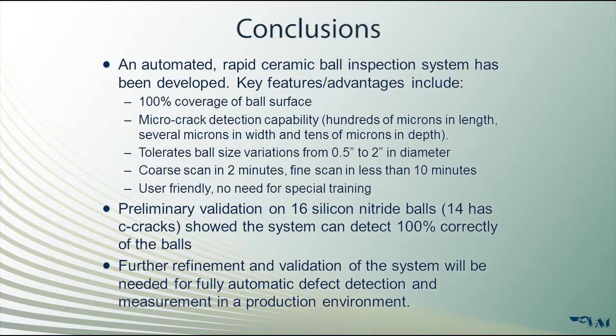detects micro-cracks of hundreds of microns in length, accommodates ball sizes from 0.5 inches to 2 inches in diameter, performs a ball scan in less than 10 minutes in most cases, and it has a user-friendly operation interface. There is no need of extensive training to operate the system.